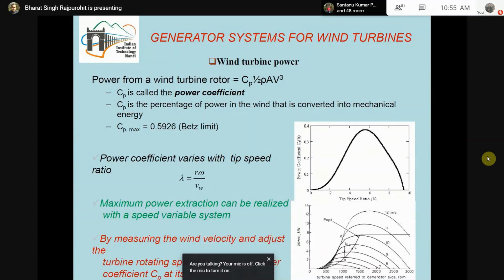Let us say we are able to achieve this point. Suddenly, the wind speed changes from 12 meters per second to 10 meters per second. Then, if we are still working at 1800 rpm, our maximum point as per the 10 meters per second characteristic is not there. It means we have to move a bit towards the left-hand side, and if we are able to achieve 1500 rpm, once again we are at the maximum point of the characteristic for 10 meters per second wind speed.